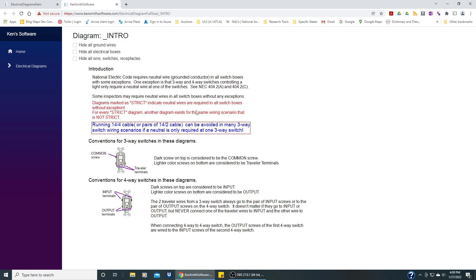The National Electric Code requires neutral wires in all switch boxes but some inspectors may require neutral wires in all switch boxes without any exceptions. Some will allow it if you have multiple three-way four-way switches, and some inspectors will only require neutrals in one of those electrical boxes.